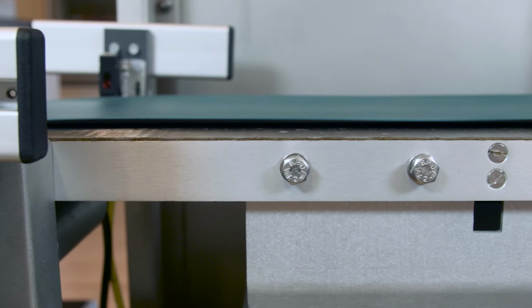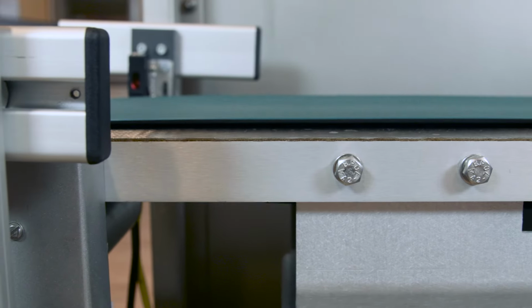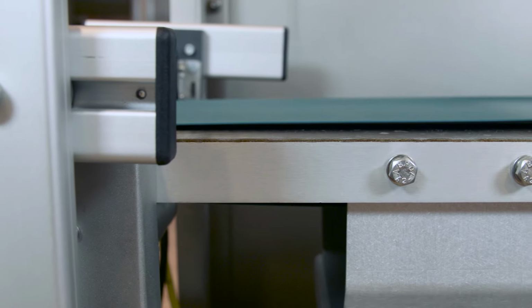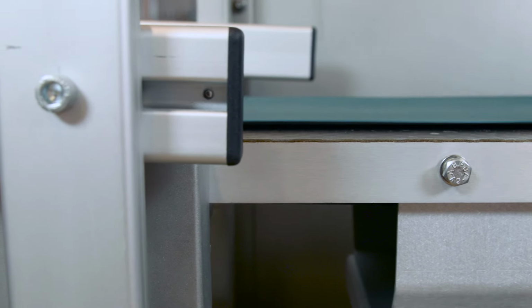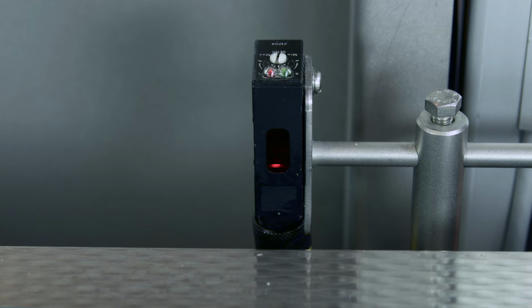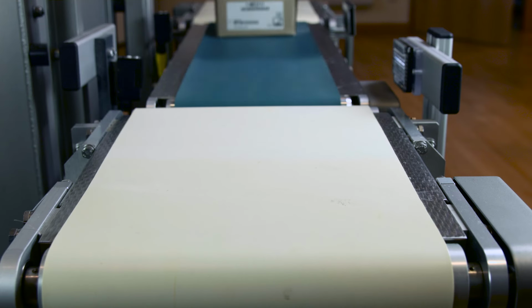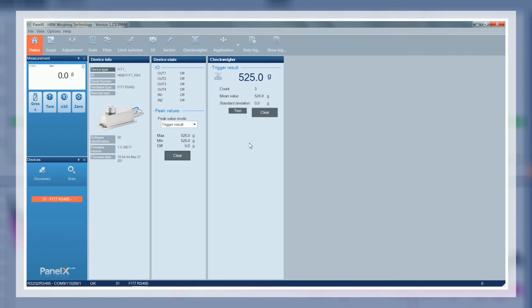We will run the same package 20 times over the Checkweigher to test our settings. During the test, the weight of our product remains the same. The captured deviations will allow us to determine how accurate our weight measurements really are, taken with the settings we configured. After 20 test measurements, we can see the arithmetic mean value of the captured weights is around the expected 525.1 grams. The standard deviation is only 0.1 gram.